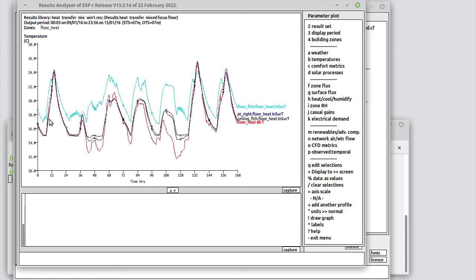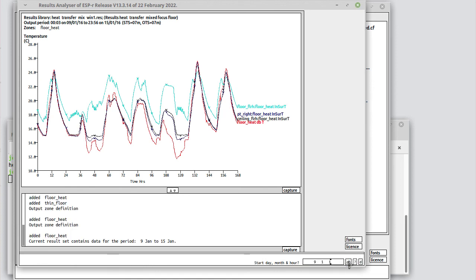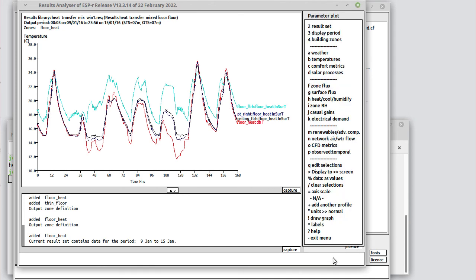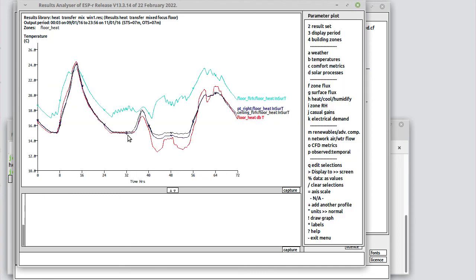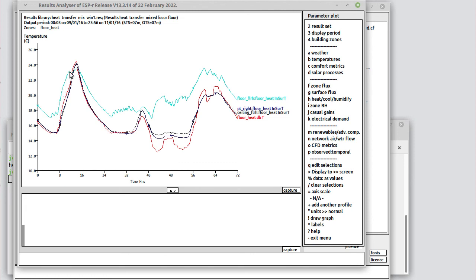So essentially we've looked at more than a week here. Let's focus down so we can see some of the patterns a little bit in greater detail. So here we're just focused on the 9th through the 11th. There's the temperature, 8 o'clock in the morning. The temperature starts ramping up. It might be about 7 or something like that that we see the floor temperature come up. The heat goes up to 24 degrees because we've overshot what was asked for.